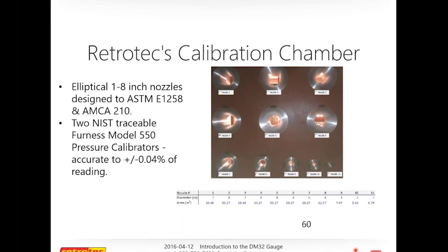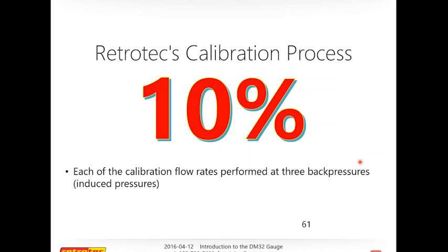So point being that even though it is always a good idea to make sure that you are still in calibration, or that you are still doing a field check on your gauge, rest assured that when you get your gauge, it has been calibrated in a chamber that meets the highest standards. So the calibration will be verified in those standards. That basically it's going to be verified at a minimum of 3 flow rates, where 1 is below or within 10% of the minimum flow measured, and 1 is above or within 10% of the maximum operating flow. Right? So, I got those backwards, sorry. But the calibration at each of these 3 flow rates is performed at 3 back pressures, and that's an induced pressure, where 1 calibration point is above or below, as I explained before.